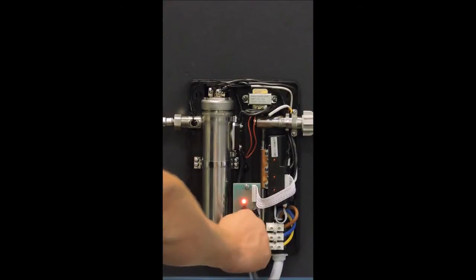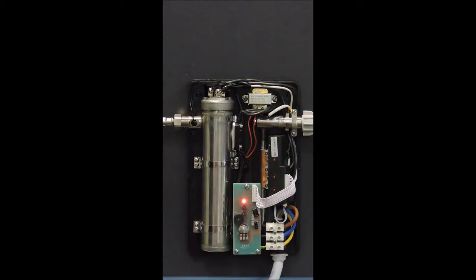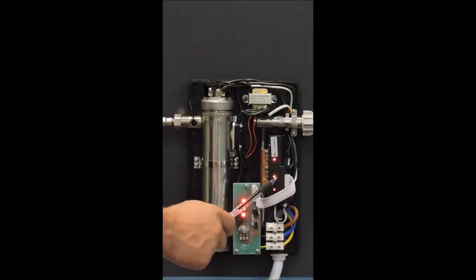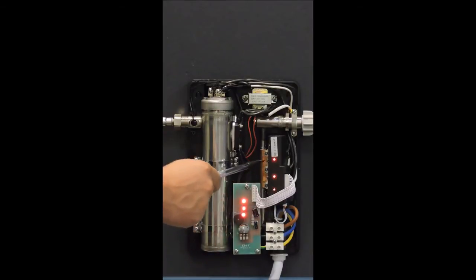If you look at the right hand side of the heater, you will see the PCB with the three lights on it. These three lights correspond to the triac that is directly across from it. The triac are like gates for the power, opening and closing according to the power needed. If a triac fails, the light next to it will not illuminate.